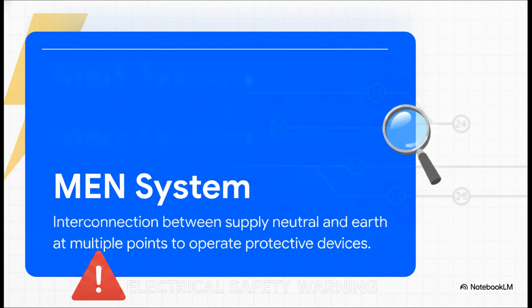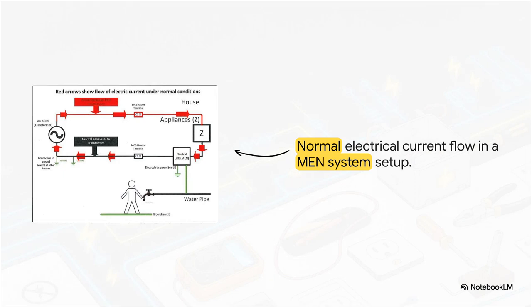But here is an absolutely critical takeaway. We can never, ever rely on the resistance of the earth electrode alone. The data is clear. Earth return impedance is almost never low enough to ensure safety on its own. If we trace the flow of electric current under normal, healthy conditions, the active conductor brings the current in, it does its work in the appliances, and then returns safely via the neutral conductor. Now, think about that MEN link connecting the neutral to the earth electrode. That is your ultimate safety valve. It keeps the voltage on earthed conductive parts, say a water pipe someone might lean against, at absolute zero.